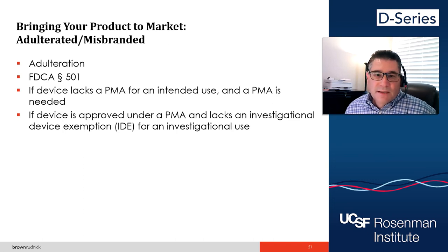If you didn't gather the data under an IDE, or an investigational device exemption, which is for your clinical trial, then that data is not allowed to be used - that evidence is not allowed to be used - your device is adulterated. If you miss a piece of documentation on step three in your process, but you still produce a perfect medical device, it's adulterated because your documentation was faulty. So that's what you need to know on that.